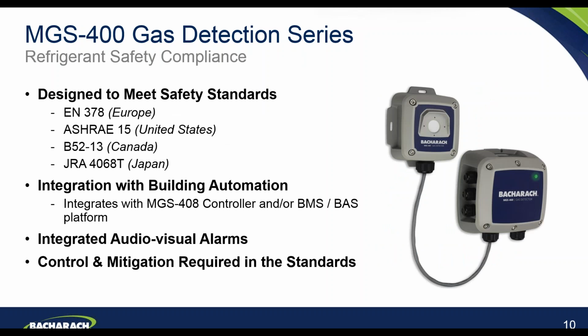Of course, when we talk about this product type in the marketplace, one of the key objectives is to ensure that we can support our customers to meet the compliance requirements of the different refrigerant safety standards. So the 400 series has been fully designed in terms of its operation, performance, and feature set to meet those safety standards. Here in Europe, of course, we are particularly concerned with EN 378. In the US, it's ASHRAE 15, and also in Canada and Japan, the relevant standards. Again, the 400 series is designed to support compliance with those standards.